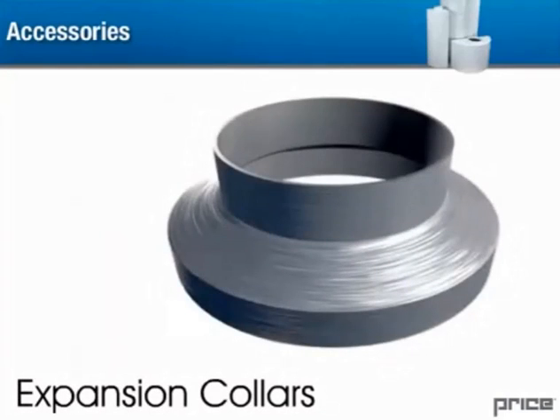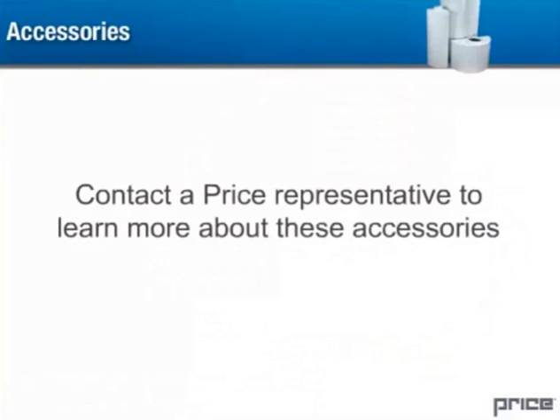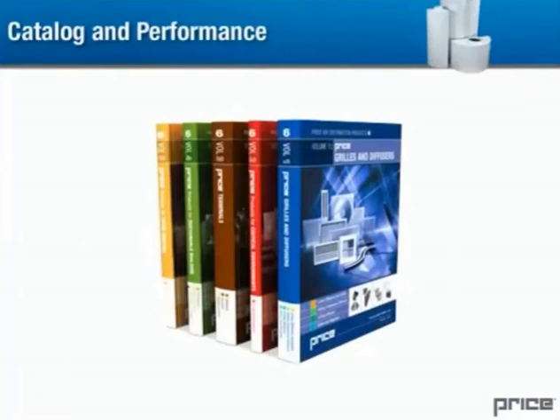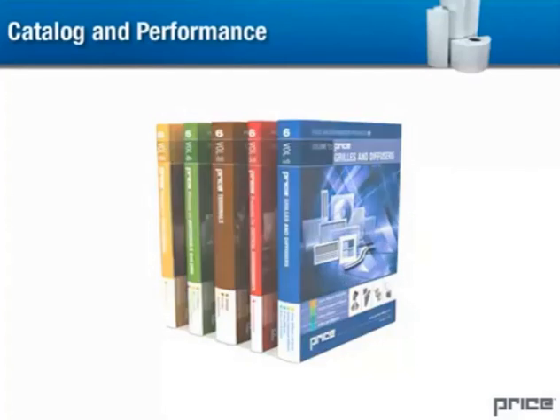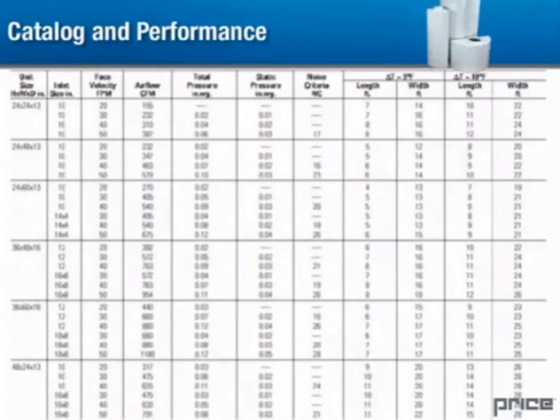Expansion collars ensure exceptional performance of the DR360 when used with smaller ductwork. Contact a Price representative to learn more about these accessories. For more information on each of these displacement diffusers, check out the performance data sheets in Price's comprehensive printed catalog. There you'll find test results and gathered data for unit size, inlet size, face velocity, airflow, total pressure, static pressure, noise criteria, and adjacent zone. As a resource, it'll help you select your diffuser and design a displacement air distribution system for any given application. Click on any of these categories to learn more.